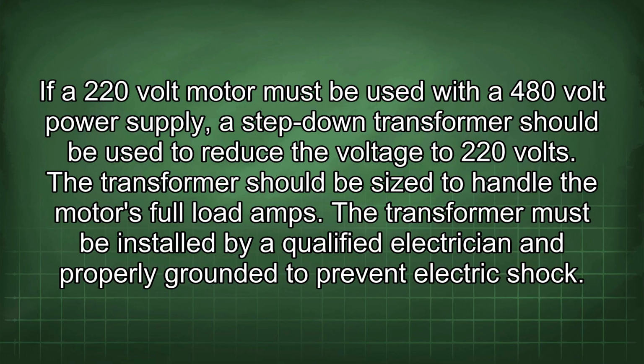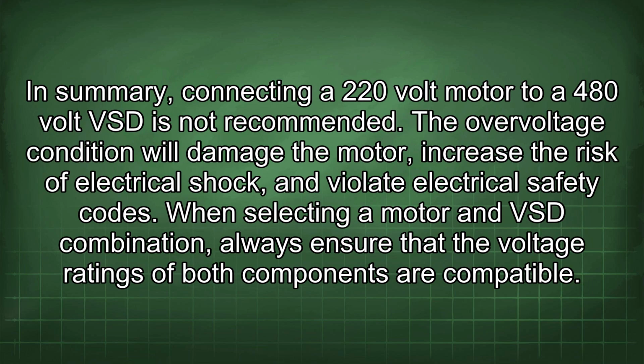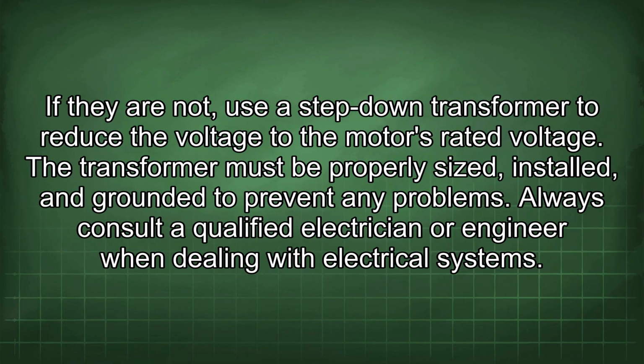The transformer should be sized to handle the motor's full load amps. The transformer must be installed by a qualified electrician and properly grounded to prevent electric shock. In summary, connecting a 220-volt motor to a 480-volt VSD is not recommended. The overvoltage condition will damage the motor, increase the risk of electrical shock, and violate electrical safety codes. When selecting a motor and VSD combination, always ensure that the voltage ratings of both components are compatible. If they are not, use a step-down transformer to reduce the voltage to the motor's rated voltage. The transformer must be properly sized, installed, and grounded to prevent any problems. Always consult a qualified electrician or engineer when dealing with electrical systems.